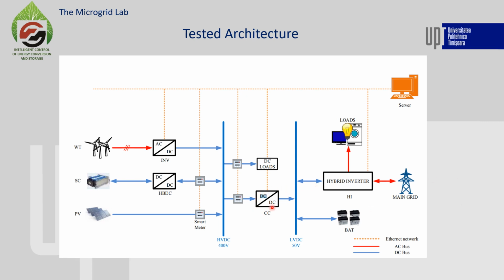The charge controller links the high voltage DC bus, where the renewable sources transfer their power, with the low voltage DC bus, where the batteries are connected. If the renewable sources cannot provide enough power, a hybrid inverter, connected to the low voltage DC bus, can take power from the main grid in order to charge the batteries, if the system is connected to the main grid.